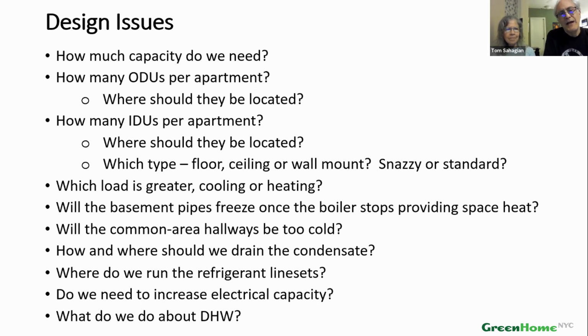How many outdoor units per apartment and where should they be located? I'll talk about that in more detail in a minute. How many indoor units and where should they go? Even though all the apartments in this building have the same footprint or a mirror image of it, two of the apartments, because of how they were internally divided, had 4 indoor units instead of 3. So you have to be mindful that how the rooms are laid out will strongly affect how many indoor units you need, their capacity, and their location.